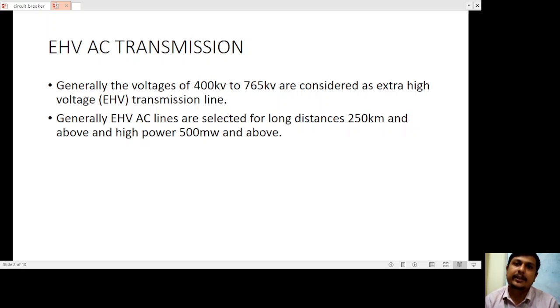Why don't we select EHV transmission for lower distances and lower power? The reason is simply cost. It is not a hard and fast rule, but roughly around 250 kilometers and 500 megawatts. If we choose lesser distance and lesser power for EHV transmission, it will not be economical. Economy is one of the important aspects in engineering - if you design anything that is not economical, it will not be sellable in the market.